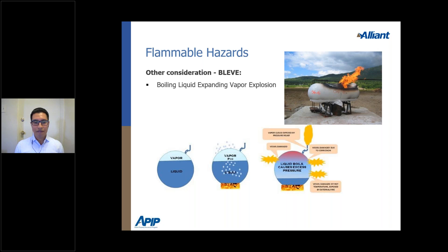Another consideration is BLEVEs — boiling liquid expanding vapor explosions. These aren't common, but worth mentioning. What happens is a complete rupturing of the vessel. This can be prevented by incorporating a vent mechanism to eject vapors directly up into the atmosphere, or keeping the pressure vessel in an enclosure to contain explosion pressure. If you ever see fire being emitted from a tank, keep your distance as the explosion could be catastrophic.